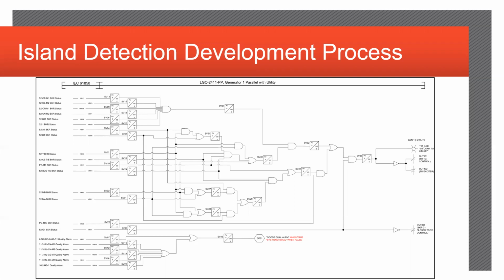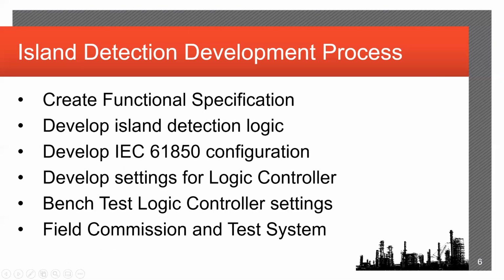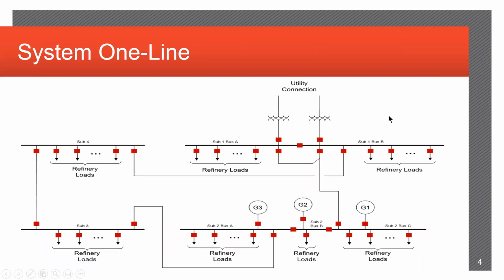Yeah, good question. The load shedding scheme that I talked about early on is an existing load shed scheme, and basically what it comes down to is anytime there was a certain couple of breakers, let me go back to my presentation, go to the single line diagram, that anytime these two breakers up here opened, I believe that's the two, because I'm a little hazy on the details with that, because that load shedding scheme wasn't part of this project. But I believe anytime that these two breakers came open, it would shed all of the refinery loads up here off of this main PDC.